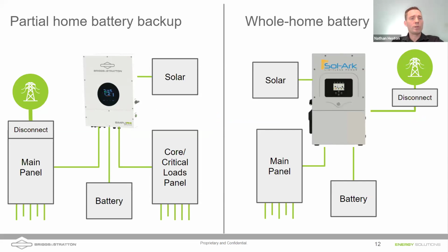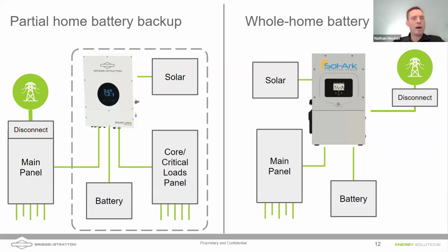And so for a smaller system like the Briggs 6K that's featured on the left side of the screen, your inverter has batteries. It does pass some of the main panel energy through to the core critical loads. But if the grid goes down, essentially what happens is the inverter isolates itself from the grid. It islands itself. And it still allows solar to come in, charge the batteries, and power the loads that are in your core critical loads panel, but it doesn't power the main panel in a grid outage.